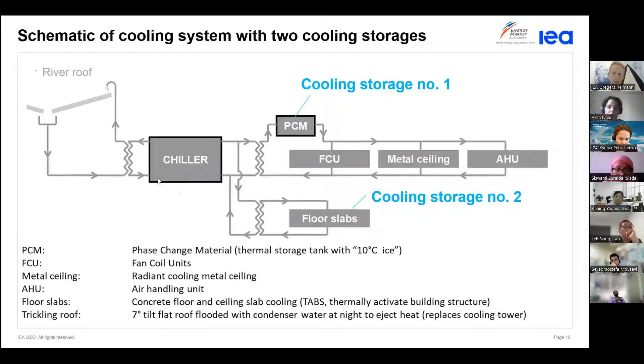And therefore the heat gets ejected to the night sky. Most of the heat was released to the sky through radiation, and a little bit through conduction and evaporation - but very little evaporation because the relative humidity is quite high at night when temperatures are lower. So the makeup water for this building was very low because we virtually didn't evaporate any water, since we emitted most of the heat to the cool night sky.